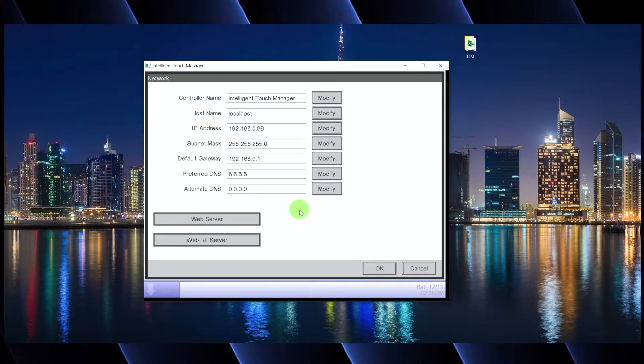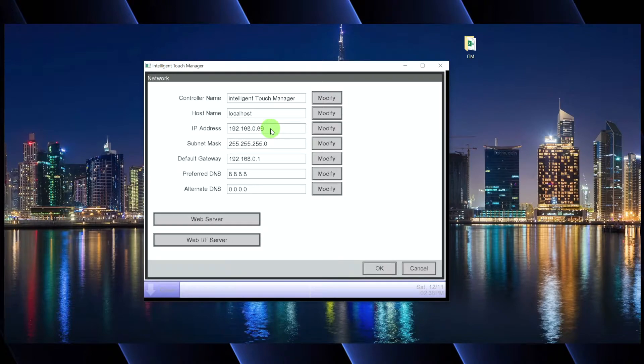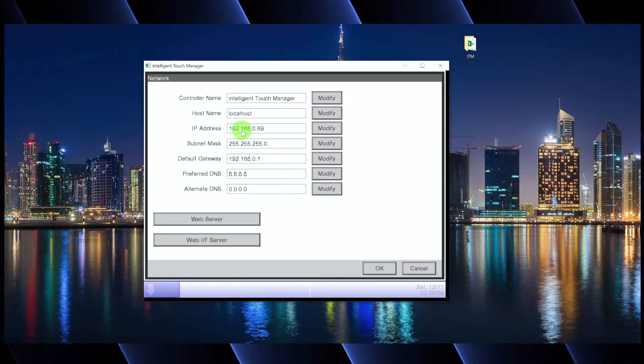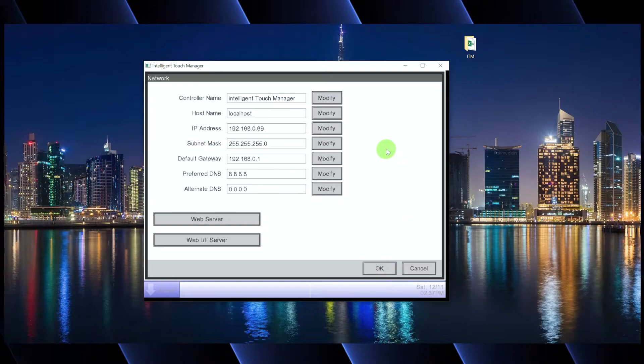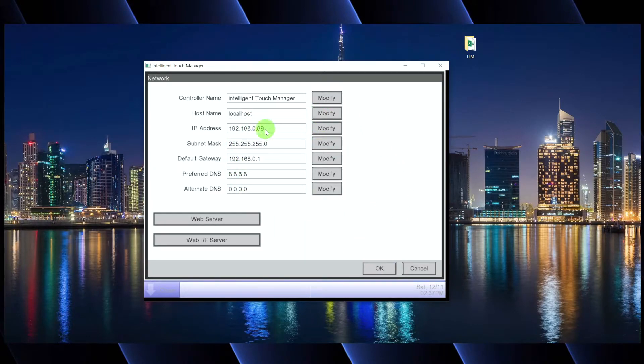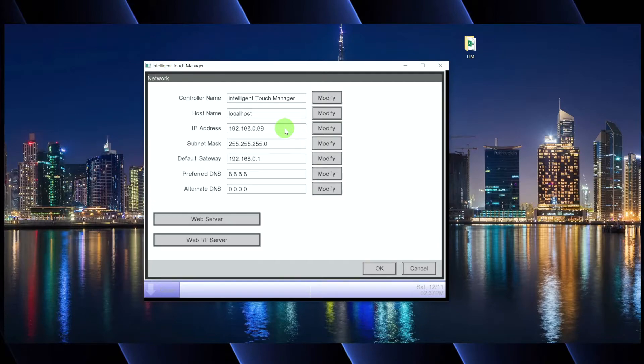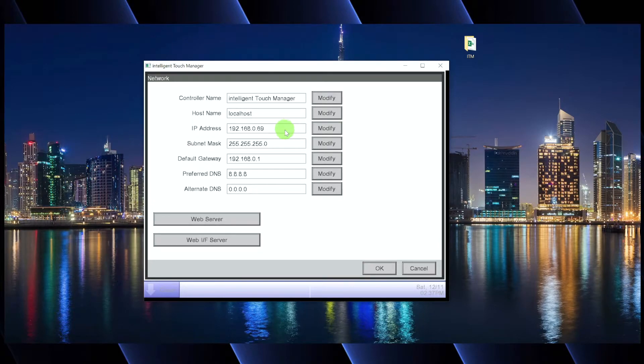Now, from this point, you're good to go. So if the IT person says, all right, I want you to set up the ITM's IP address as 192.168.0.69, then great. When I click OK, this is going to reboot. And when it reboots, it's going to have this static IP address. The ITM cannot do a dynamic or changing IP address. It has to be programmed with a static IP address.